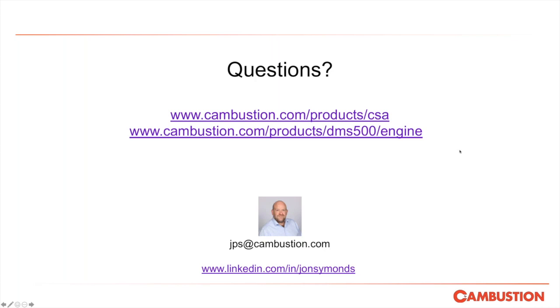Although we'd always recommend you have your instrument serviced and calibrated, of course. But before that, we probably need to have the heated line back and upgrade that to take the higher temperature of 191. But yes, the nice thing about it is it just inserts in the existing dilution system, and you just have a new software disk, and that's pretty straightforward.